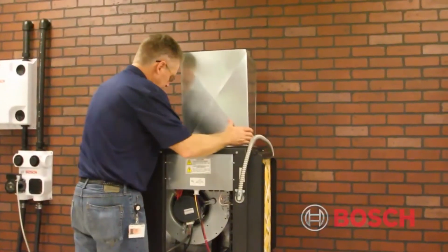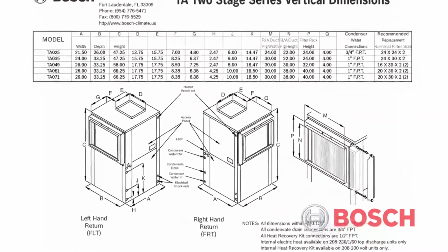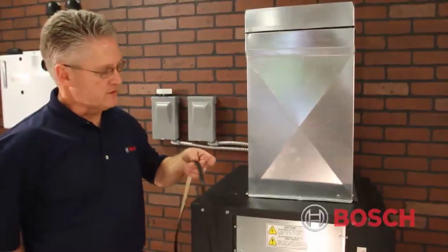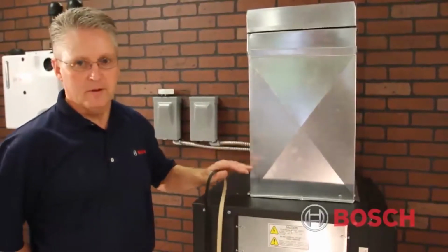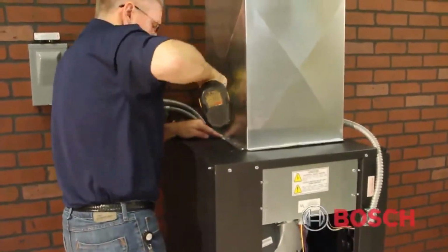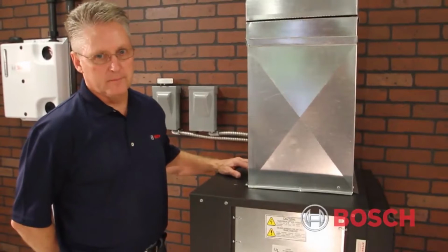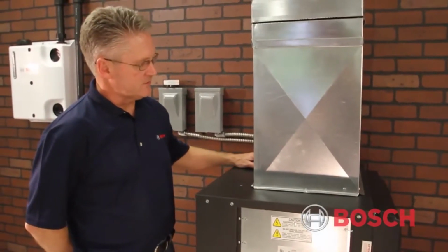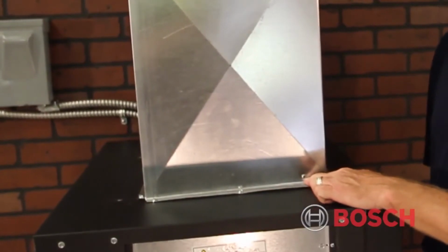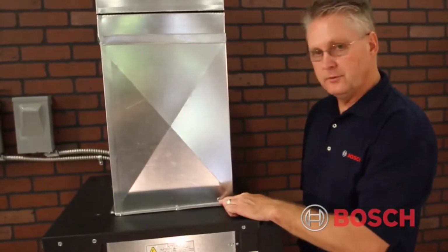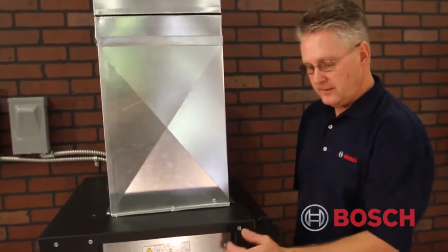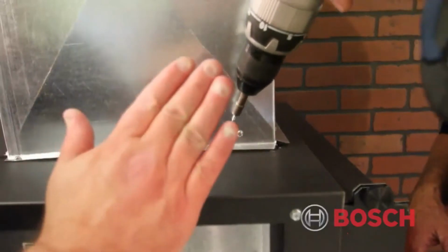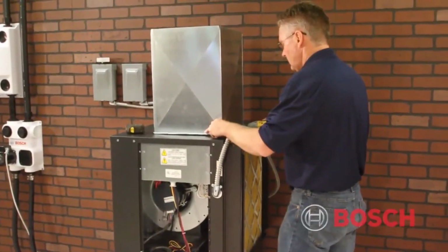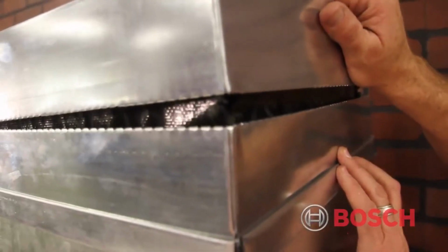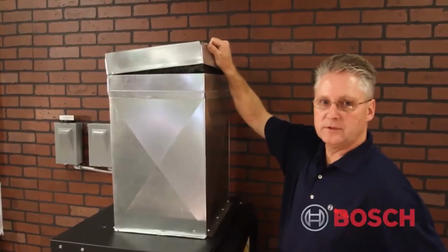What we've done is we've installed this supply plenum on top of this unit. The dimensions for this supply plenum are in the spec manual. We put some foam insulation in between the plenum and the top plate so we don't have any air leakage. You notice that we have some screws located in the top plate going around the front side and also the left side of this. Notice the different locations of these screws. This is through the top plate of the unit. This is through the duct flange. Right underneath this top plate is the evaporator coil. Never want to screw down this way. Always screw horizontally going toward the duct flange. A supply flexible connector is recommended on all metal ductwork systems.